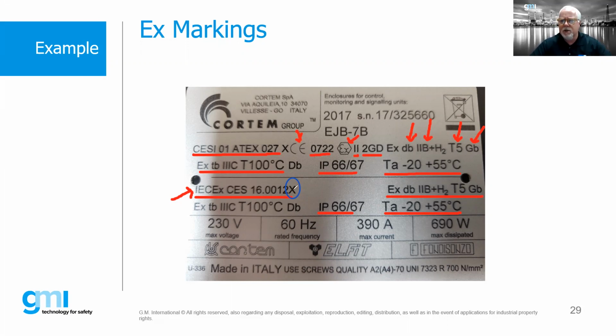Did the contractor install it in accordance with the conditions for safe use? One good example: cable glands. Cable glands will generally always have an X condition. That means if you look up cable glands, any of their X conditions, regardless of the brand, will say something to the effect of suitable for fixed installations only, meaning I cannot use that cable gland with, say, a portable tool. But there may be additional requirements, meaning that gland also may have a requirement in which the cable must be clamped within 300 millimeters to meet a pull-out requirement.